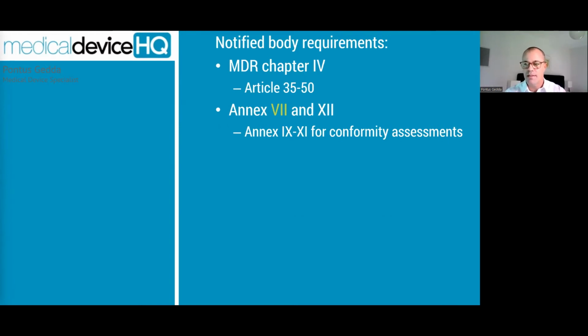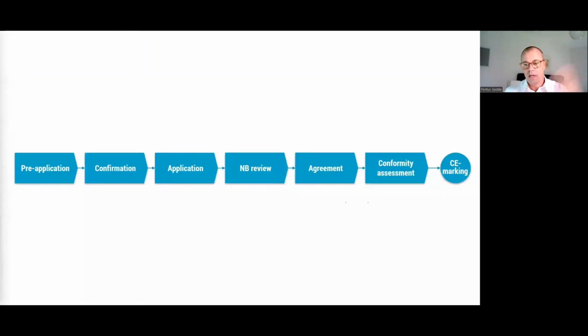Quite boring, but it is worth the effort, because this explains how the notified body shall act in relation to the manufacturer for their application, onboarding, and certification under MDR. So let's say you have now found a notified body that has the applicable MDA, MDN, MDT, and MDS codes that I just explained. Then the application process, which is a bit complex, is divided into several steps. Those typical steps are laid out here.